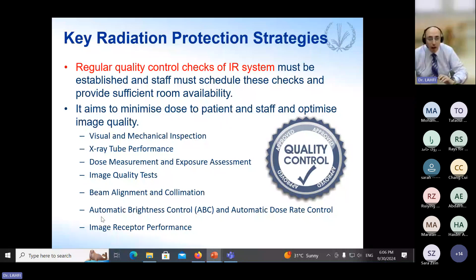For example, if any faulty timer appears, it can lead to an extremely increased dose for the patient and the staff. So it's very important to check the X-ray tube performance, the dose measurement and exposure assessment, the image receptor performance, and so on.